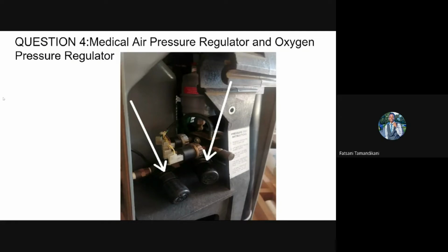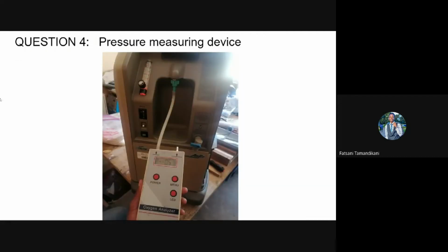After adjusting the regulator, the pressure should be around 58 kilopascals, and you can use any pressure measuring device to verify the pressure. You can use a pressure gauge, or if you have a 2-in-1 oxygen analyzer that measures the pressure or the purity, you can also use that one as shown in the graphics. Now, when making the adjustments to the patient outlet pressure, you need to disconnect the pressure measuring tool and reconnect it every time you make an adjustment so that you can see the new pressure.